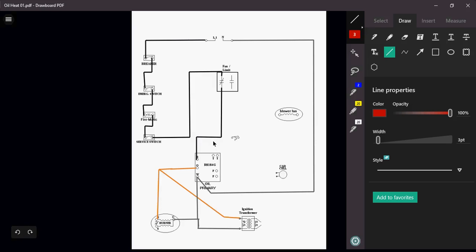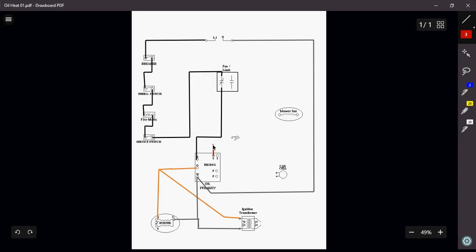So, I'm going to do my thermostat. You'll see on the primary control, you have a thermostat TT terminal here. That basically just stands for thermostat. Now, some people may ask, the thermostat operates off of 24 volts. Where's my transformer? Well, the transformer is actually inside that primary control. So, we're bringing in power, which is not only going to be sending 120 volts out to my burner so that I can spin and my ignition transformer so that I can ignite the oil, but I'm also going to be sending power to my 24 volts side of my control circuit so that I can power up my thermostat.